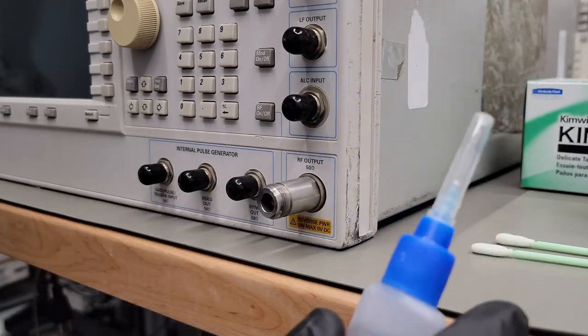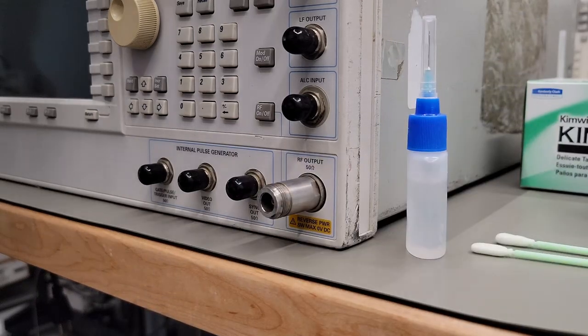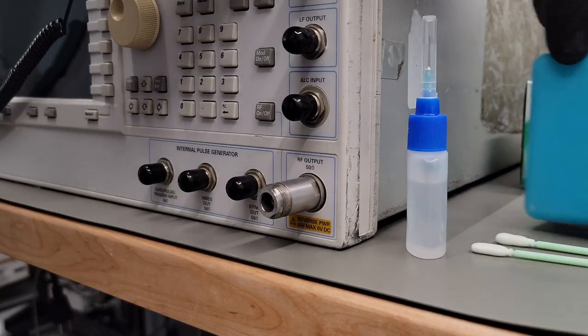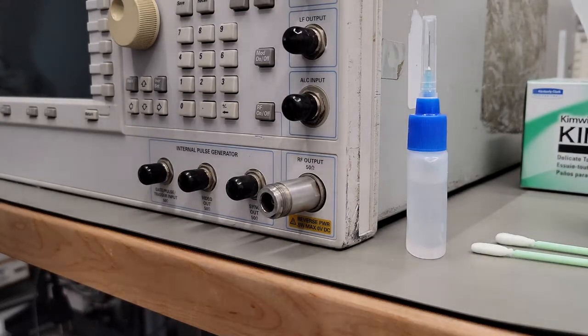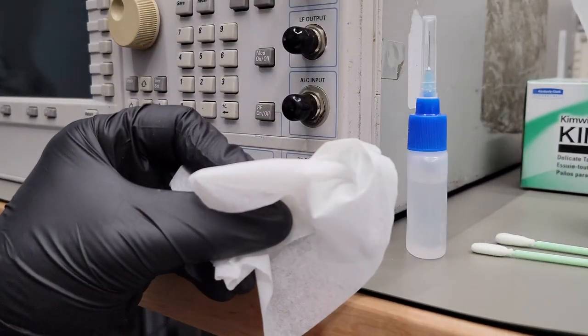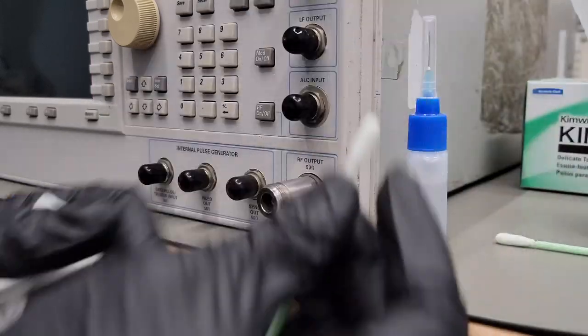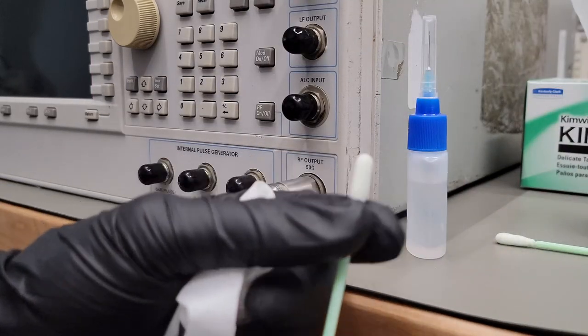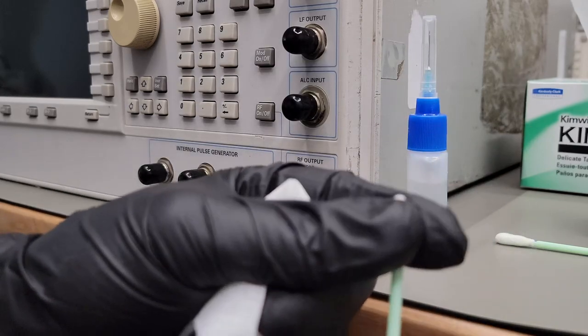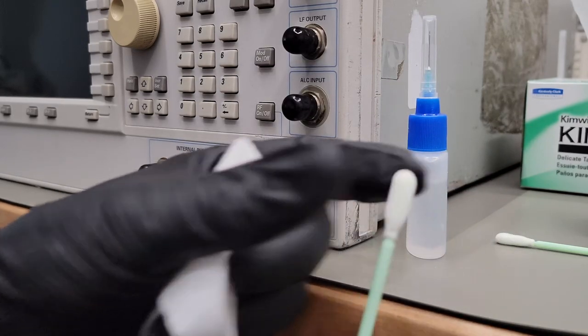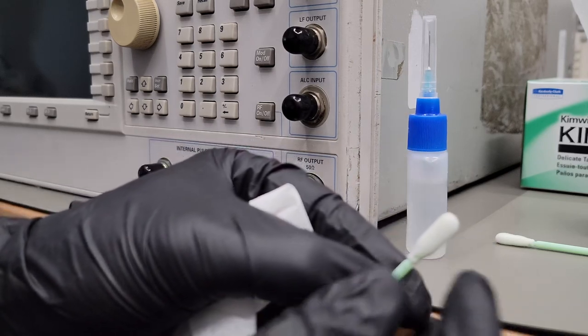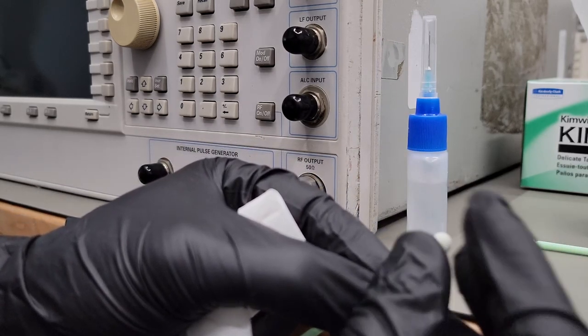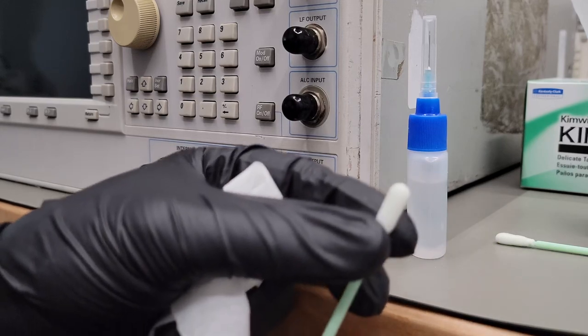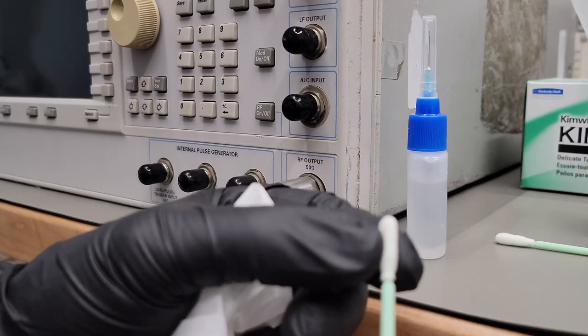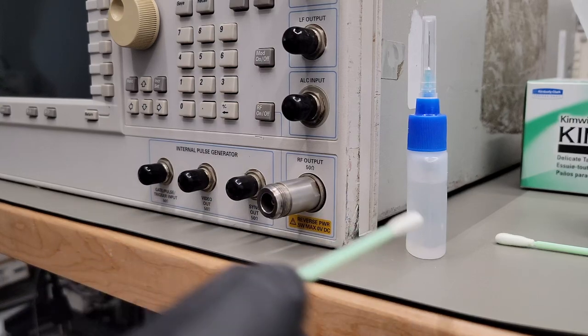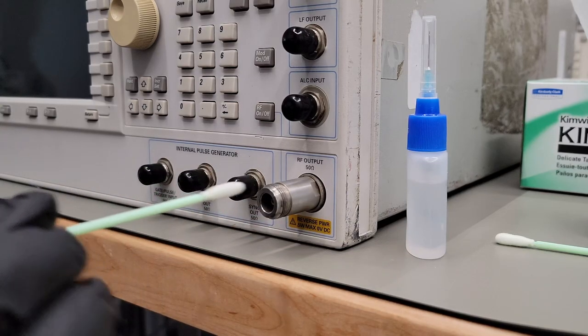And I have that in two containers here, a needle applicator, and then I also have just a little pump bottle here. And the cleaning implements I use, Kim wipes, of course, and then these little foam tip swab sponges, and make sure they have a nice cushiony foam tip. I don't like to use Q-tips because the tips are round and that cloth material will actually break up and get stuck in certain places. This is not fibrous at all. It's a foam and it has a rectangular shape. So it's actually very good for getting around that center conductor.